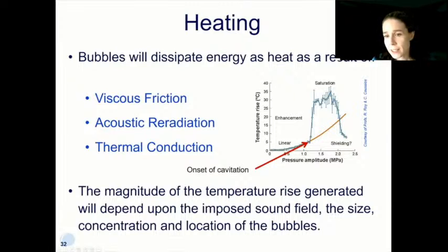So what you're seeing here is the temperature rise measured in the liquid close to the bubbles as the amplitude is increased. At low pressure amplitudes, we see a linear heating curve, which is what we'd expect. But at this point, which is the cavitation threshold, suddenly the temperature rise jumps quite dramatically. And that's due to this thermal enhancement effect of the presence of bubbles. That's extremely useful in therapeutic ultrasound because it means we can accelerate the rate of heating in tissue and hence reduce the duration of the treatment.